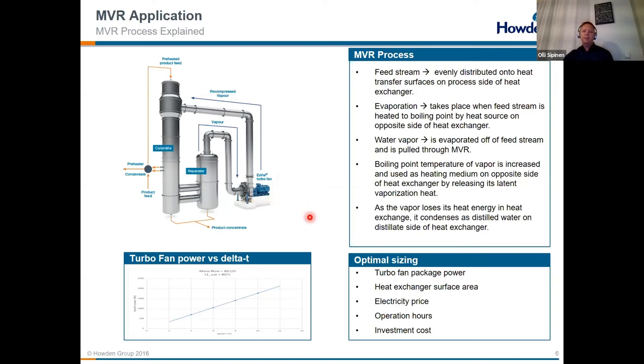And then if we look at the sizing of this kind of an evaporation system, so the compressor power intake is quite linear as a function of the required pressure rise or delta T there. So if we have a high delta T there, we are taking more electrical power, but we can reduce the size of the heat exchanger.